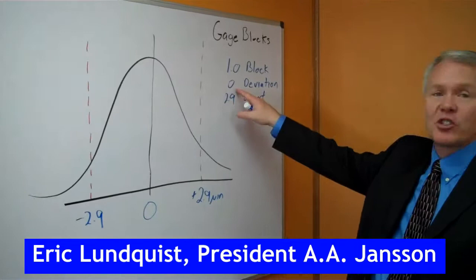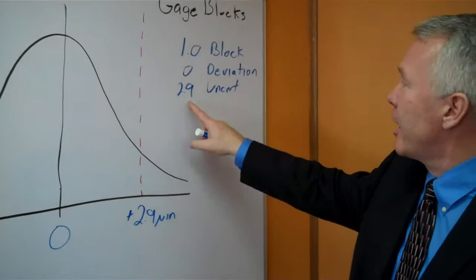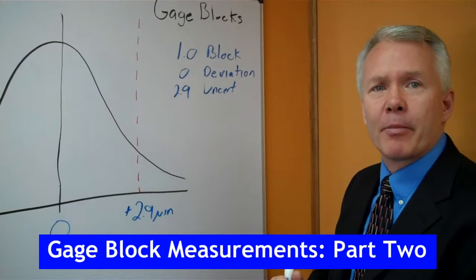To recap what we just went over, we measured a one-inch gauge block that had zero deviation, so we reported that it was exactly one inch, and we showed you how to use the formula to actually calculate that it had an uncertainty of 2.9 millionths.